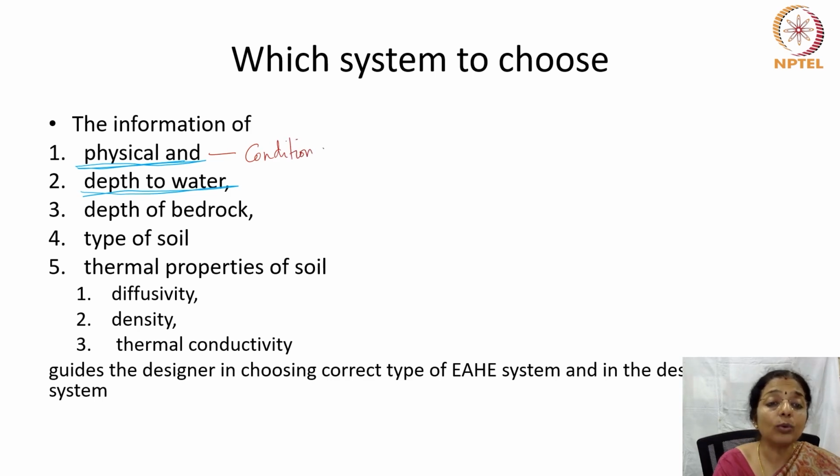We need to understand depth of water, because what will happen when you start digging, say the water table is very high? You will start getting water when you start digging, then how can you lay the pipe? So depth of water is important for us to understand. Third is depth of bedrock.